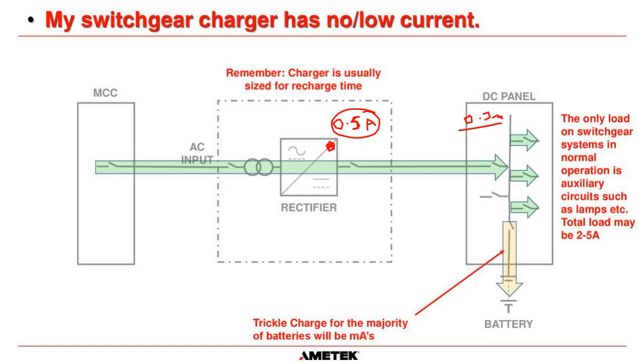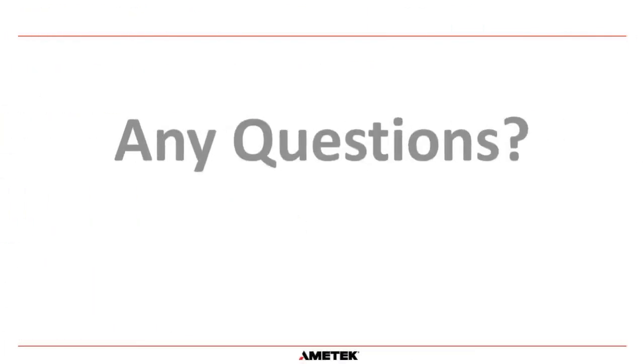And that gives lots of false alarms on systems. And believe me, I've been called out to so many systems. Oh, we've got an alarm on our charger. And I go out there and I realize that it's the low current alarm, and there's nothing wrong with the system whatsoever. And I just have to tweak the setting for the low current or disable it, because I'll have a conversation with the plant and say, look, you really don't need that low current alarm. Okay. And that's the last one. So any questions? I hope that was informative. Let me go through the questions in the chat bar. And while I'm going through that, if you have any other questions, just let me know.